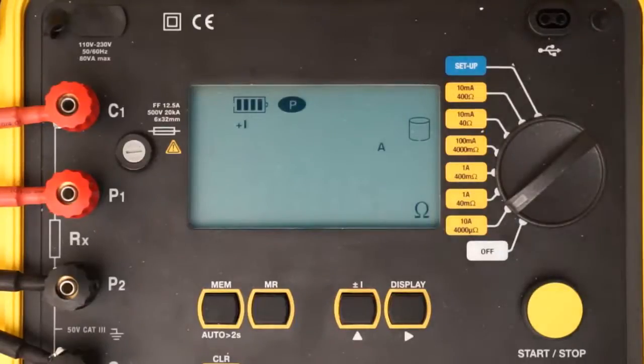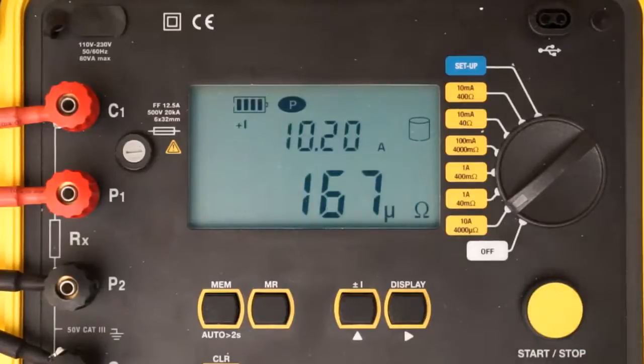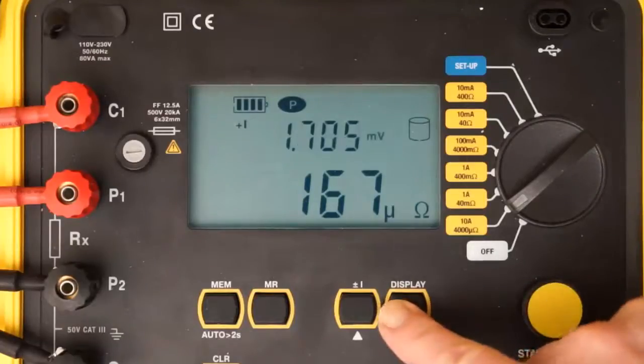To begin the test, press the start-stop button once. After a moment, the resistance and current measurements appear in the LCD. As you can see, current is slightly over 10 amps, and resistance is approximately 167 micro-ohms. Note that you can also display the test voltage by pressing the display button. In our example, test voltage is approximately 1.7 millivolts.